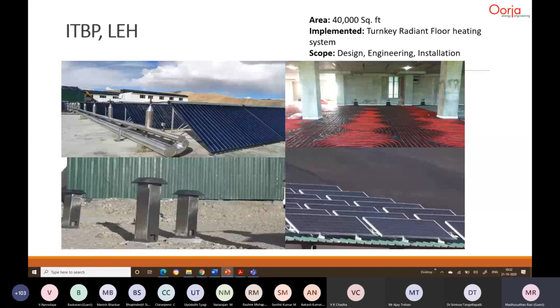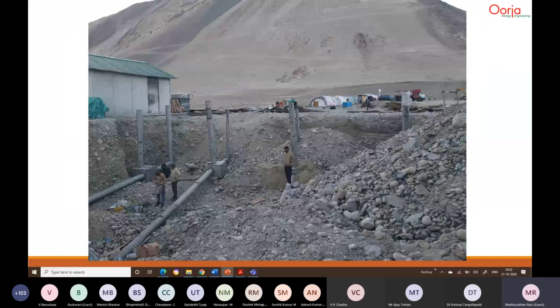To heat that air would mean using some form of solar energy. Instead, we used the Earth's heat, constructing earth tubes where the Earth at 5 to 6 meters depth has a phase lag of about 3 months from the surface temperature. So Earth temperature at this level stays positive—when it's minus 40 outside, it's around plus 5 to plus 10 degrees centigrade down there. This lets us heat the air without using any energy generation system like solar thermal or solar PV, providing positive temperature air which can be further heated a little and then given to the soldiers as fresh air.